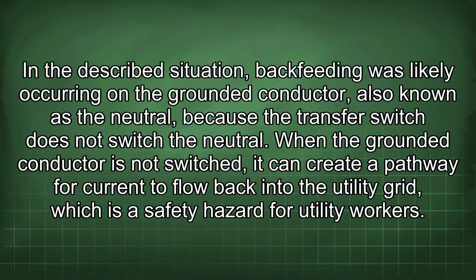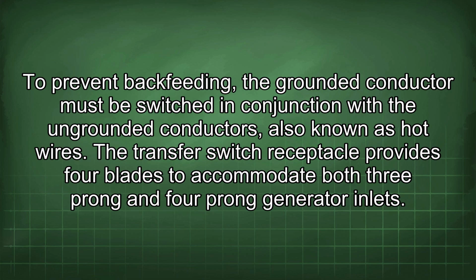In the described situation, backfeeding was likely occurring on the grounded conductor, also known as the neutral, because the transfer switch does not switch the neutral. When the grounded conductor is not switched, it can create a pathway for current to flow back into the utility grid, which is a safety hazard for utility workers. To prevent backfeeding, the grounded conductor must be switched in conjunction with the ungrounded conductors, also known as hot wires.